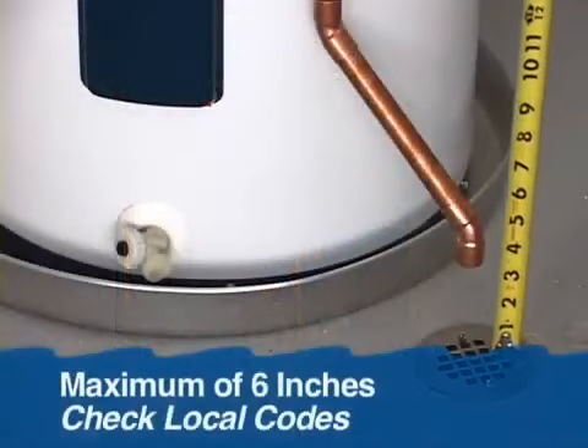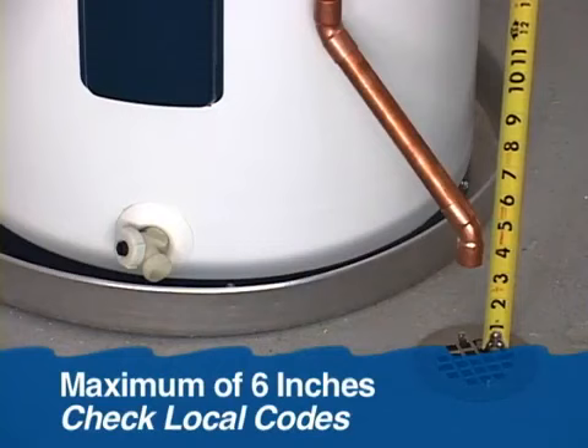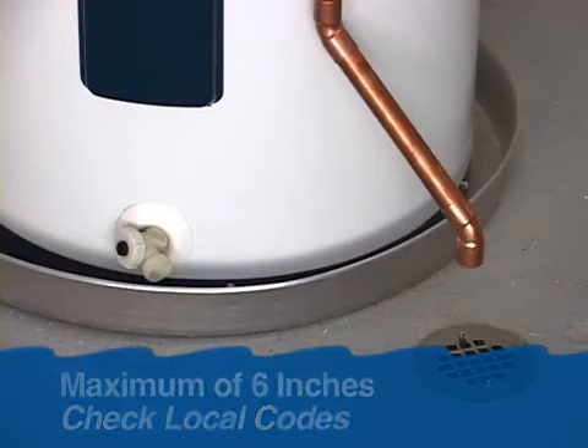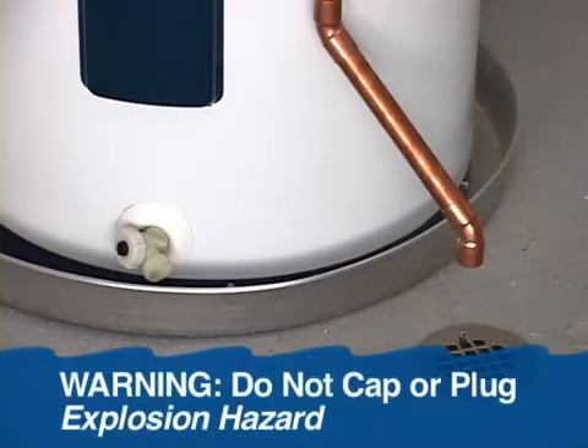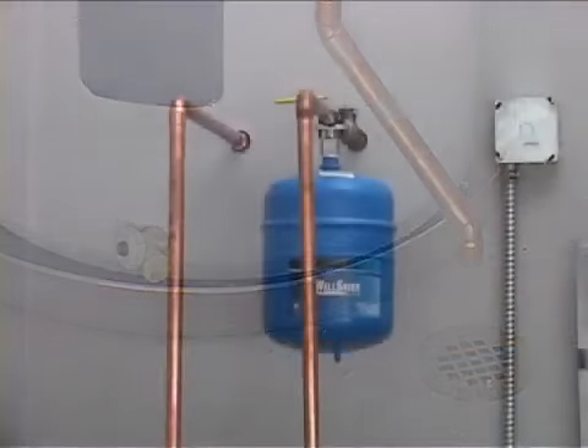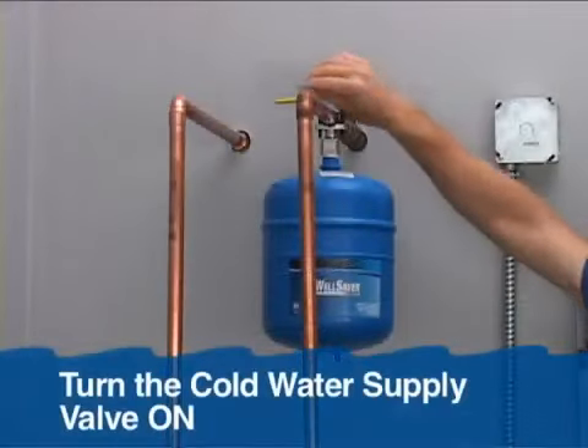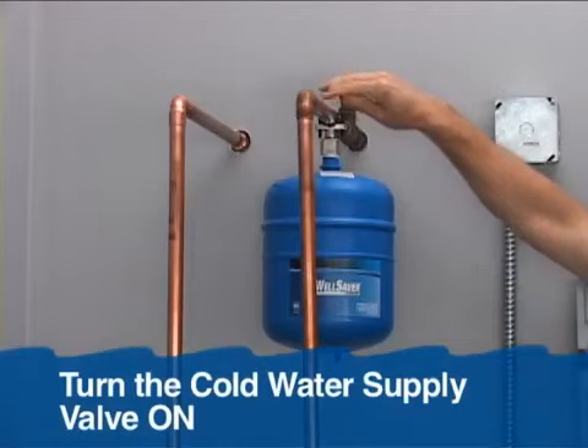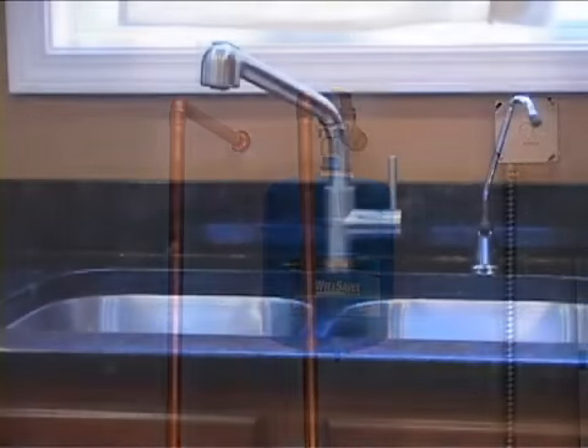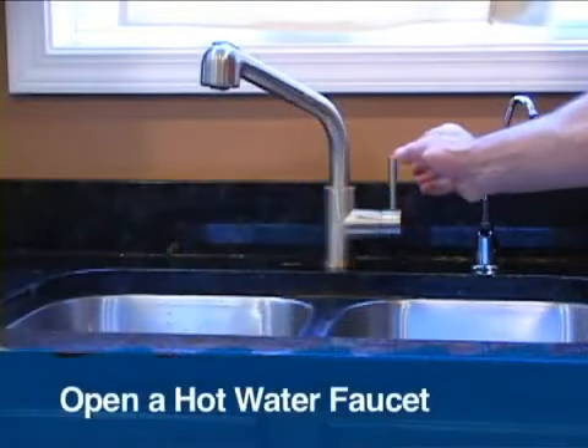The opening on the discharge pipe must not be more than 6 inches above the floor. This pipe must never be capped or plugged. Refer to the printed installation instructions for construction details and important safety information. Once the piping is complete, turn the cold water supply valve on and fill the tank. Open a hot water faucet to let the air out of the tank.